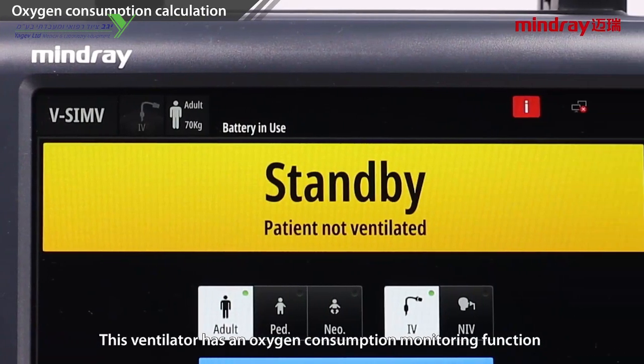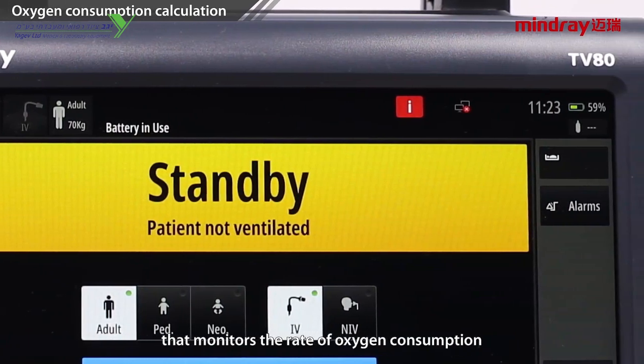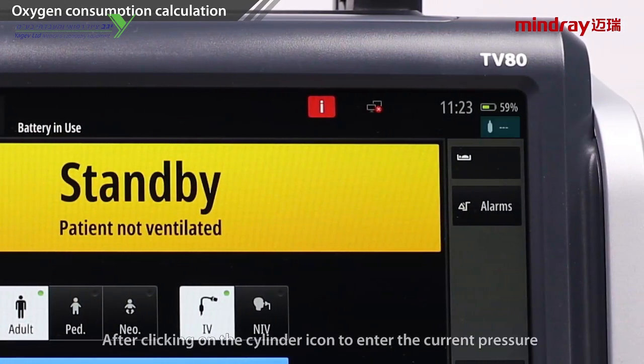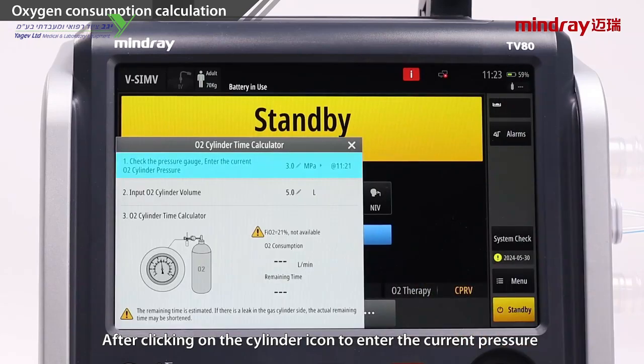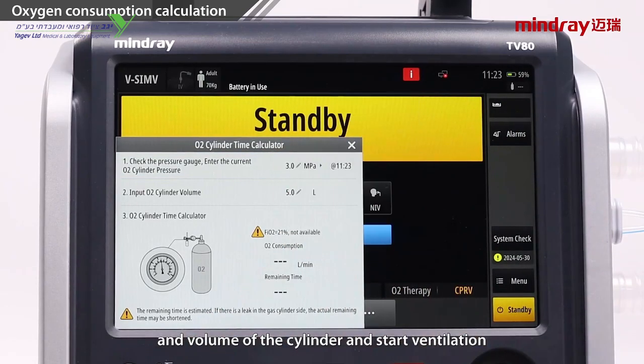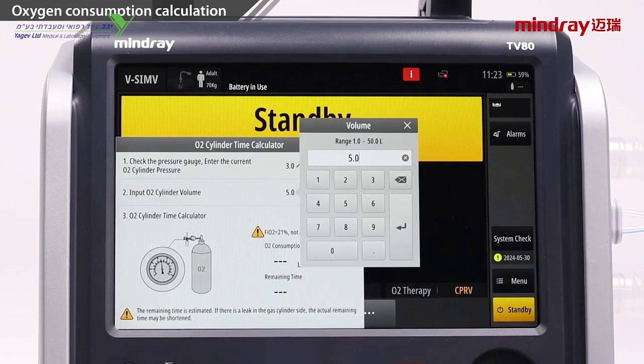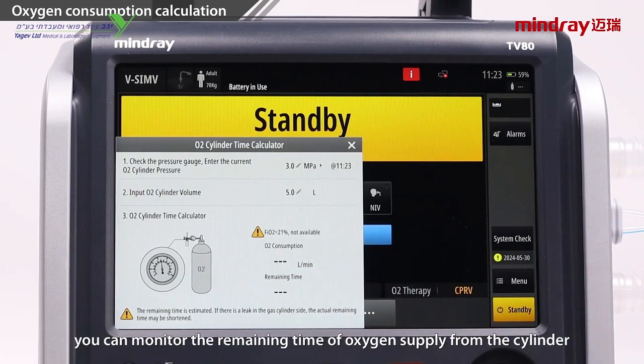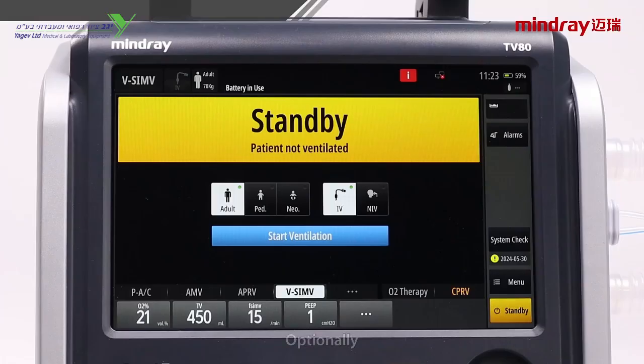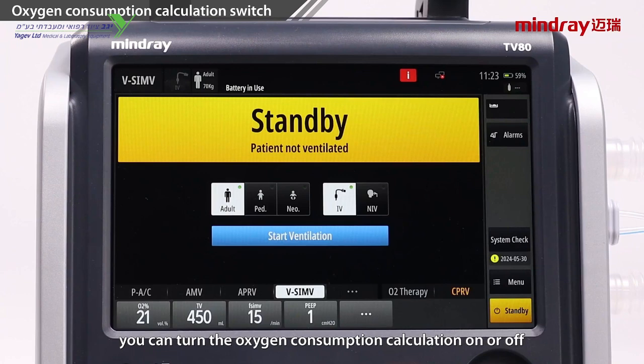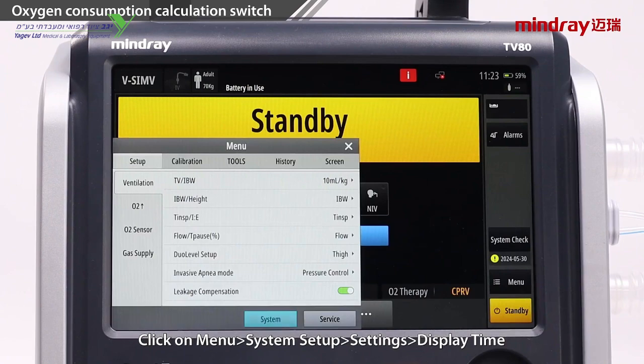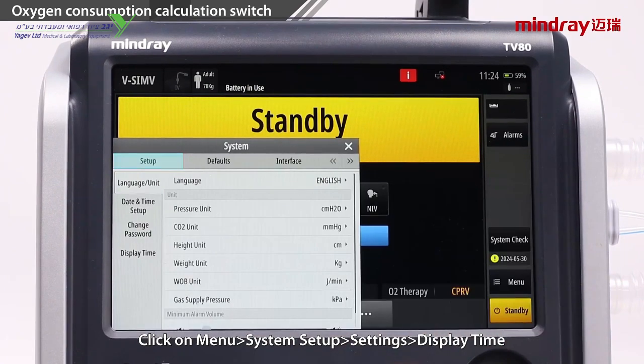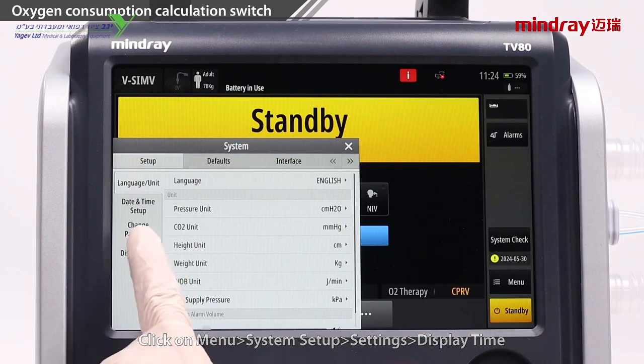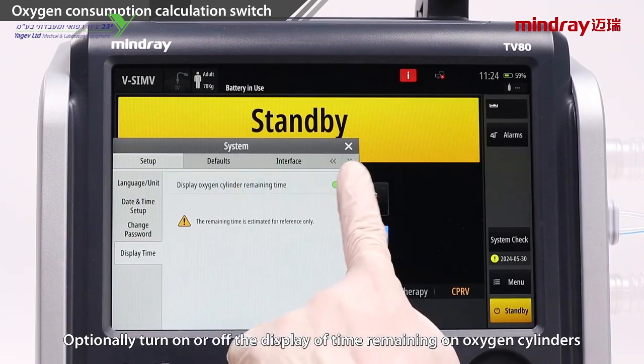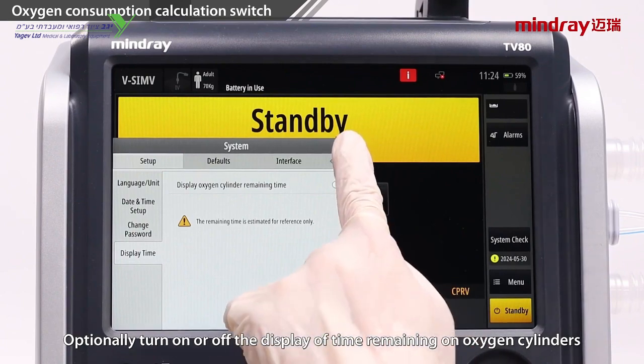This ventilator has an oxygen consumption monitoring function that monitors the rate of oxygen consumption. After clicking on the cylinder icon, enter the current pressure and volume of the cylinder and start ventilation, and you can monitor the remaining time of oxygen supply from the cylinder. Optionally, you can turn the oxygen consumption calculation on or off. Click on Menu, System Setup, Settings, Display Time. Optionally turn on or off the display of time remaining on oxygen cylinders.